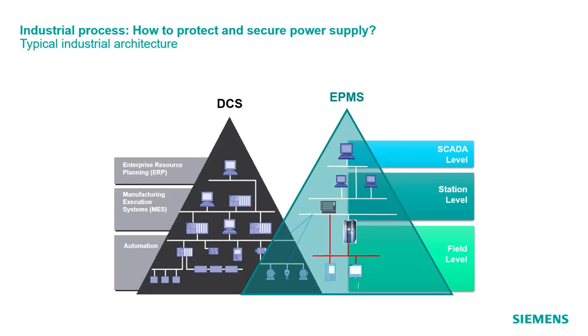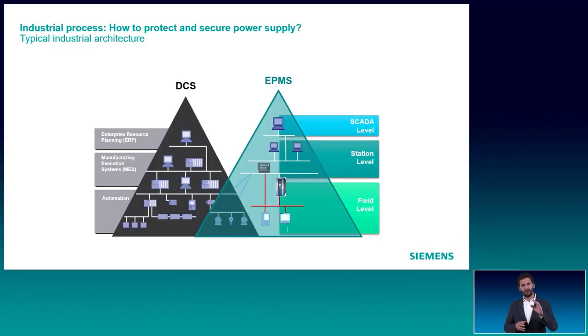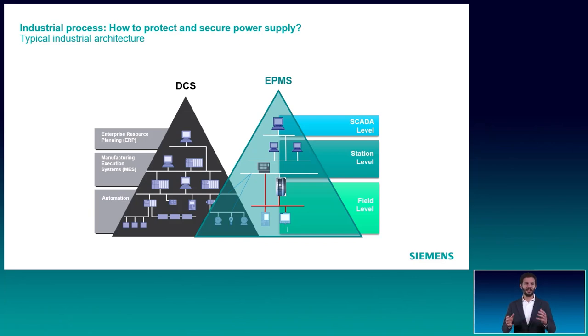If we look now in more detail at the system architecture, we see the different levels of the DCS and EPMS. Looking at the EPMS, we see three different levels: field level, addressing protections and power meters; station level, where substation controllers and local HMIs are installed; and SCADA level, running the electrical control center. During the next minutes, we will be focusing on the relevance of the field level in electrical infrastructures applied to industrial environments, namely the different application cases supported by protection relays and their main advantages in the context of critical operation.